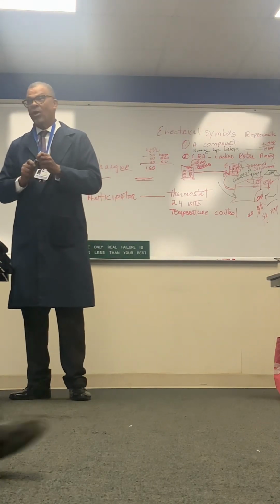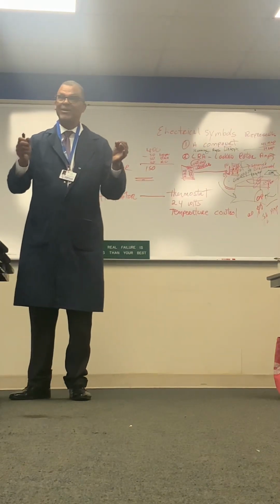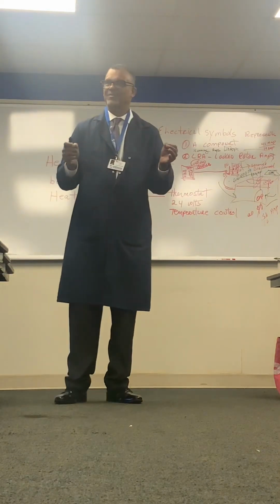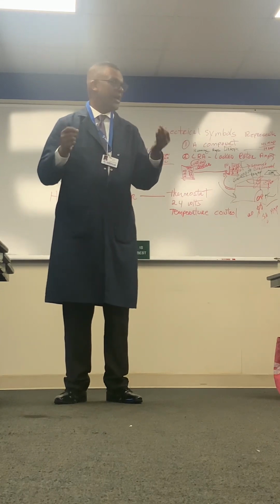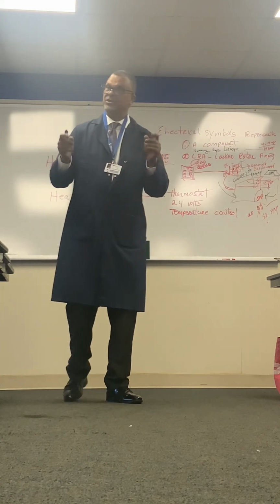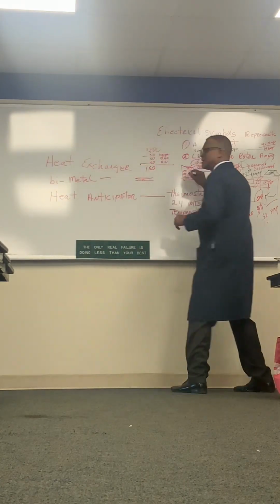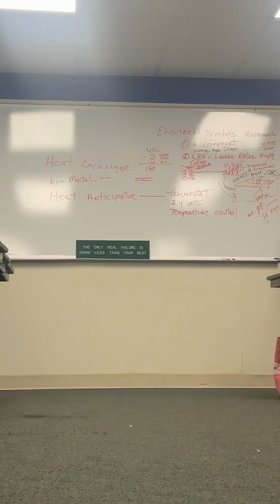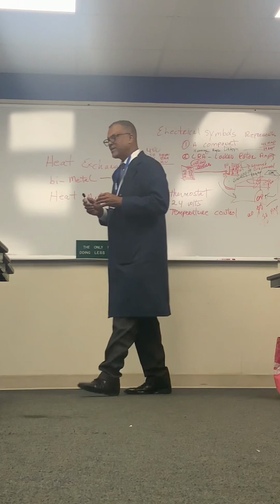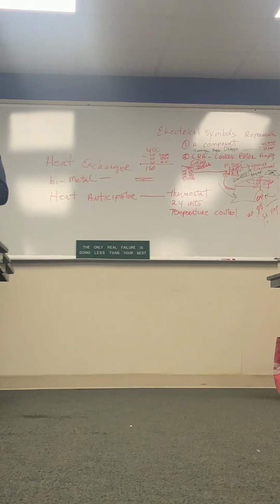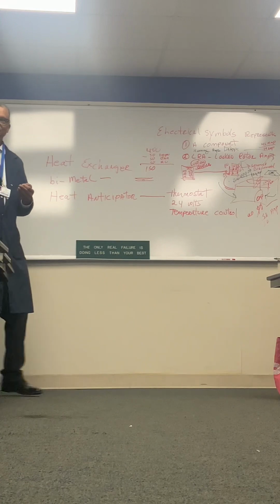But if you test it at L1 and L2 at the disconnect, it tells us, it doesn't tell us anything, Harrison. It lets us know that I do have 240 volts from the breaker box. Some people call it a load center because all the loads are connected to a particular breaker switch. So if I have it at L1 and L2 on the disconnect, I have it at the unit. How could then I get it to the compressor and the fan? How does it get to the compressor and fan?